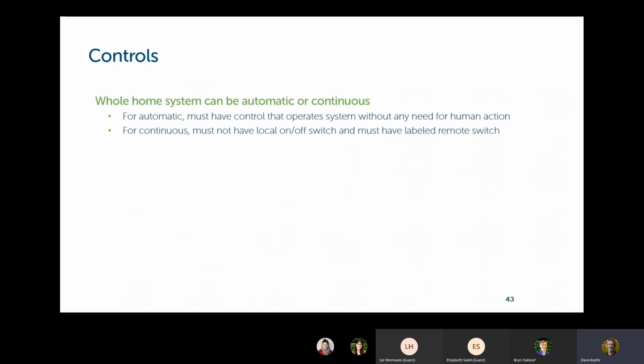If that's your scheme, you're not allowed to have an on-off switch locally, that is, in the bathroom right there where it would be easy for someone to shut it off. You do have to have an on-off switch, but it has to be remote and it has to be labeled. So if you're going to go this route, this probably is a separate switch, perhaps next to the electrical panel, that just can be a very simple on-off switch, but it has to be labeled as a ventilation system.